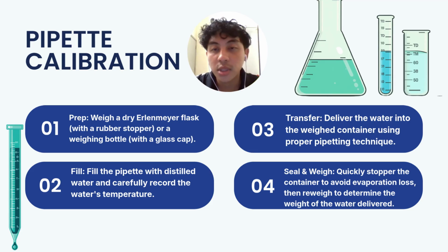All right. Now I'm going to talk about ways to calibrate a pipette. The first step is the preparation. We must weigh a dry Erlenmeyer flask with a rubber stopper or a weighing bottle with a glass cap. Second is the fill process, where we must fill the pipette with distilled water and carefully record the water's temperature. Third is the transfer process, where we must deliver the water into the weighed container using proper pipetting technique. Last but not least, we must quickly add the stopper to the container to avoid evaporation loss. Then reweigh to determine the weight of the water delivered.